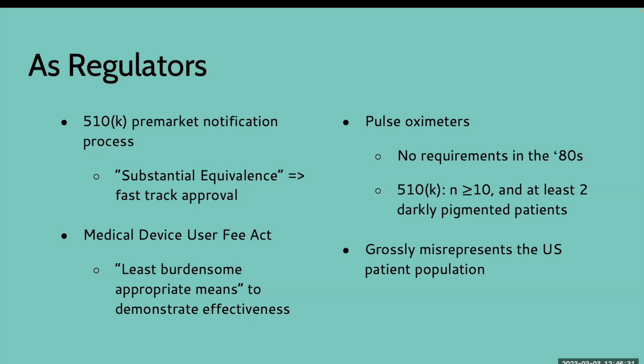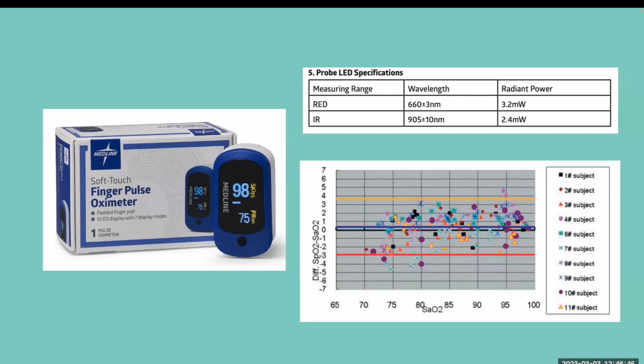What does this look like for Highland Hospital? This is the pulse oximeter we distributed in our EDs on the left. And in their manufacturer's documentation, it reports only using those same 2 wavelengths of light and testing on only a dozen subjects with high variability and no stratification based on either race or skin tone.